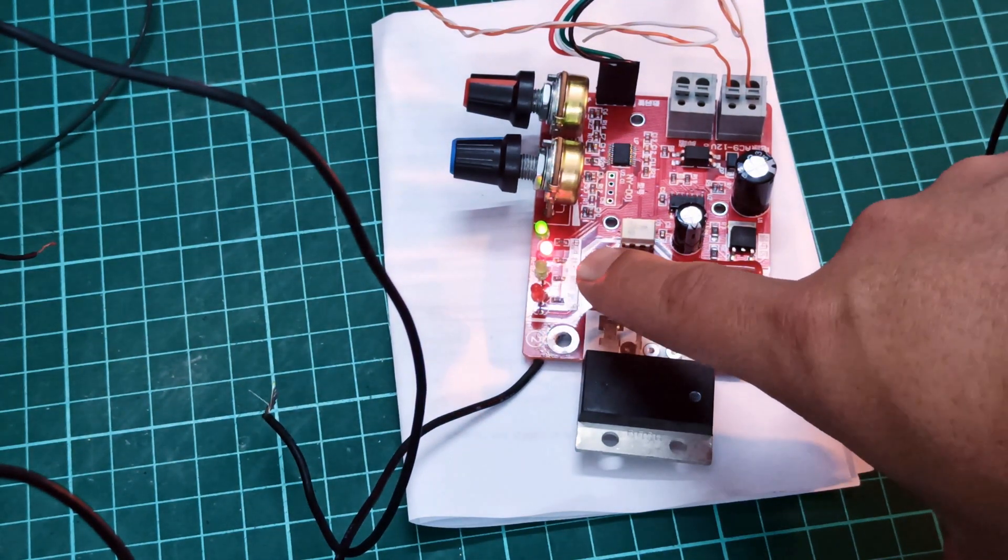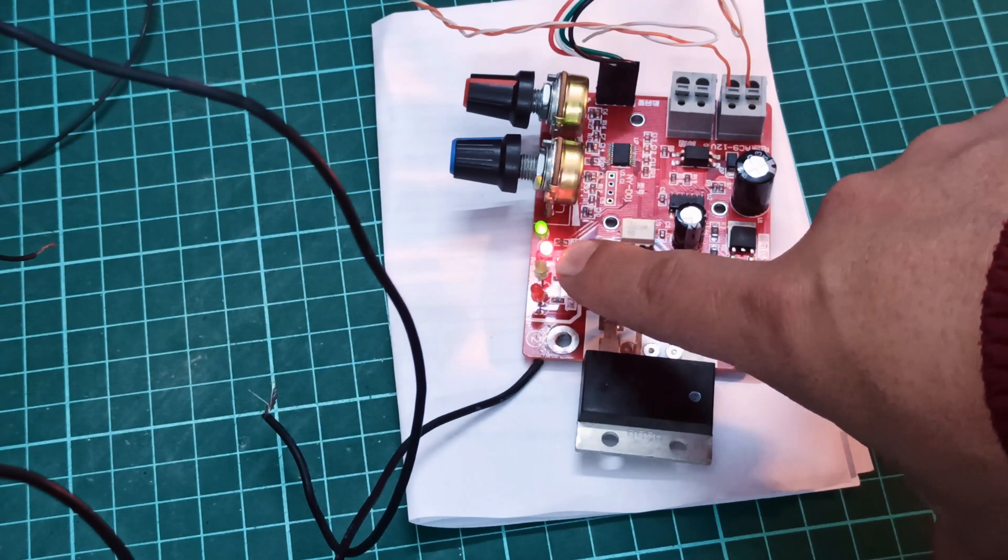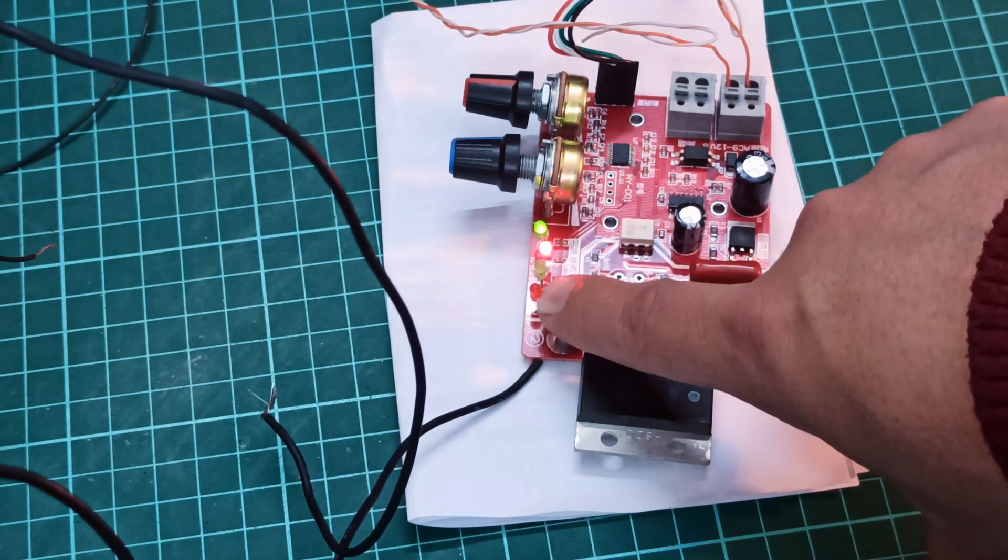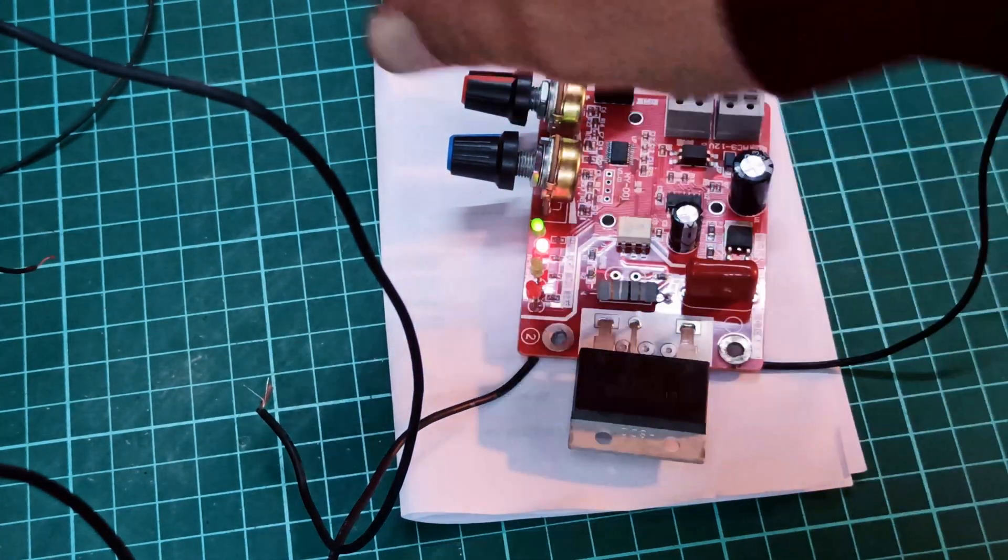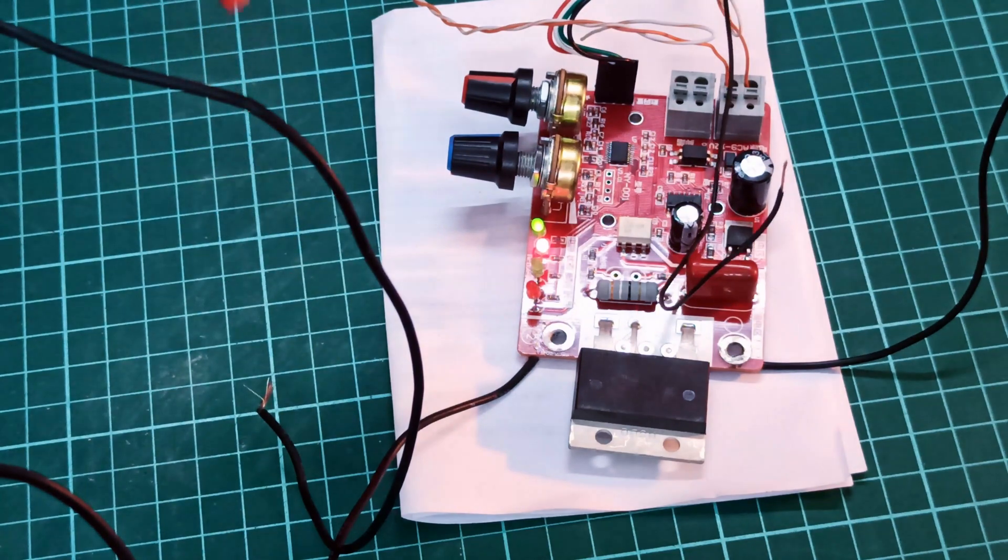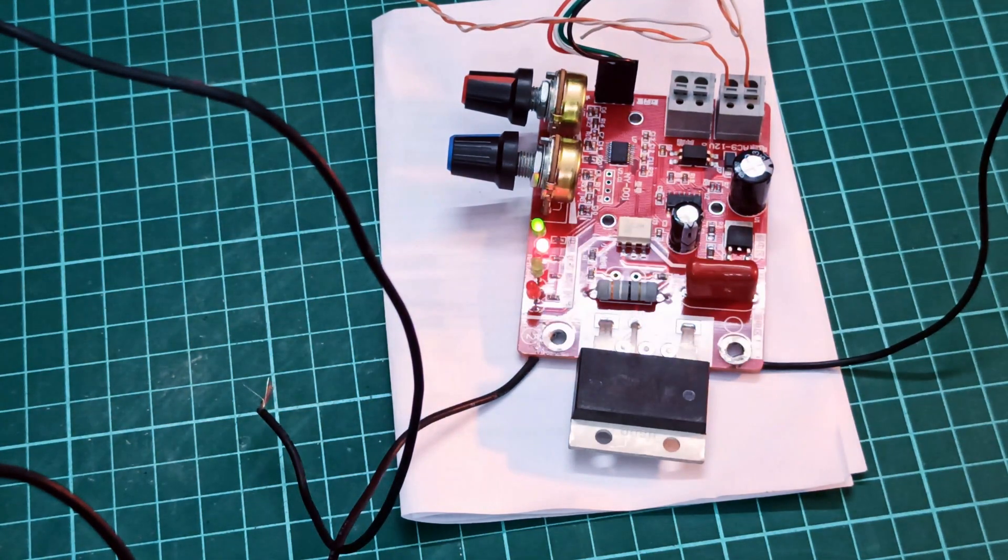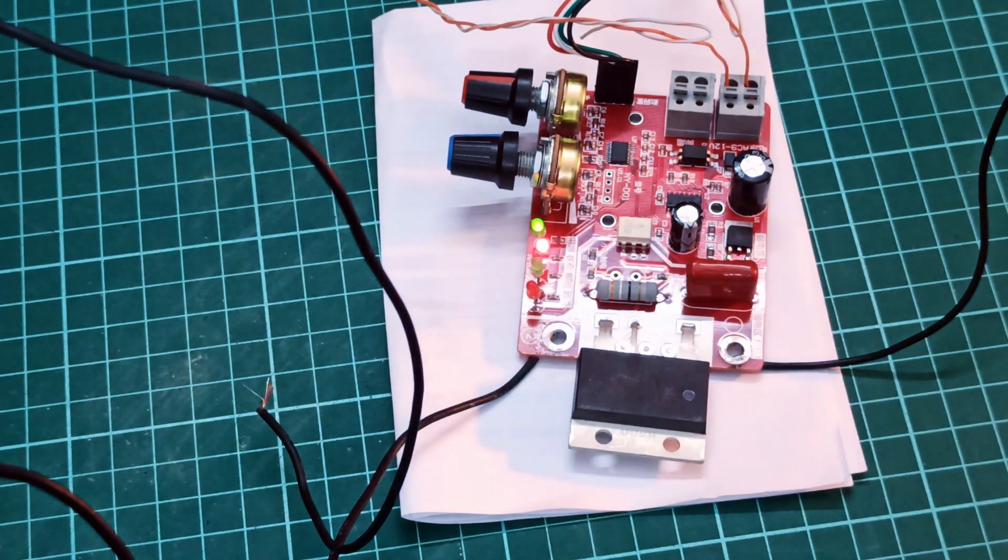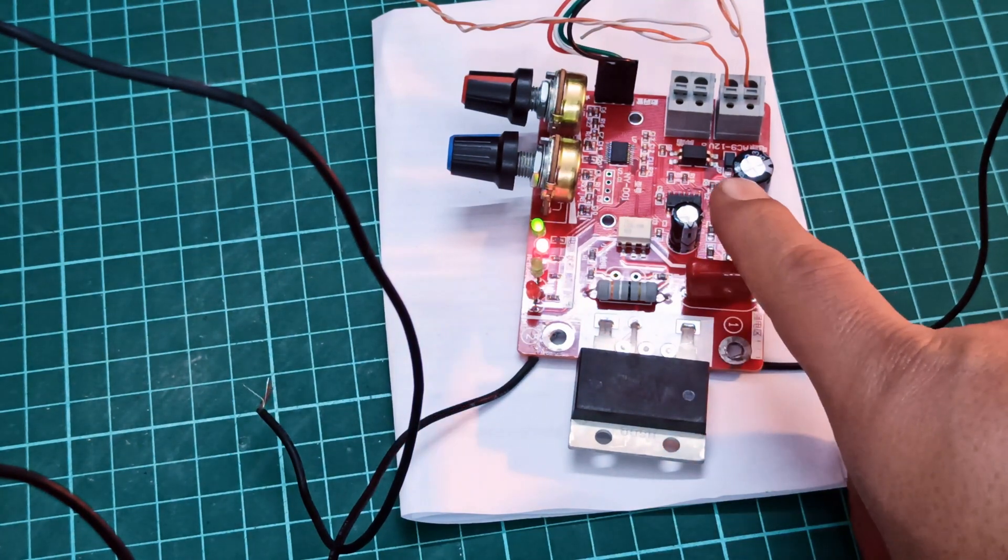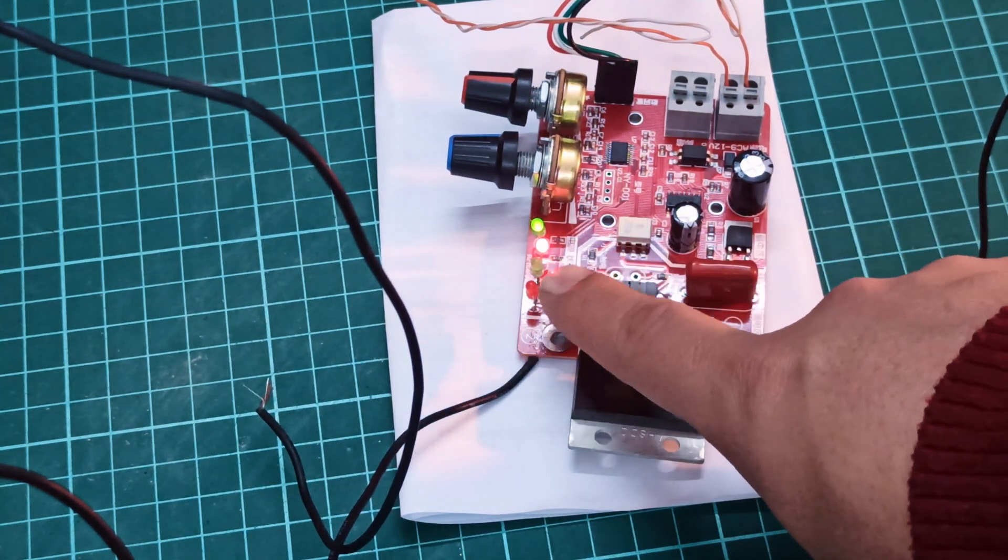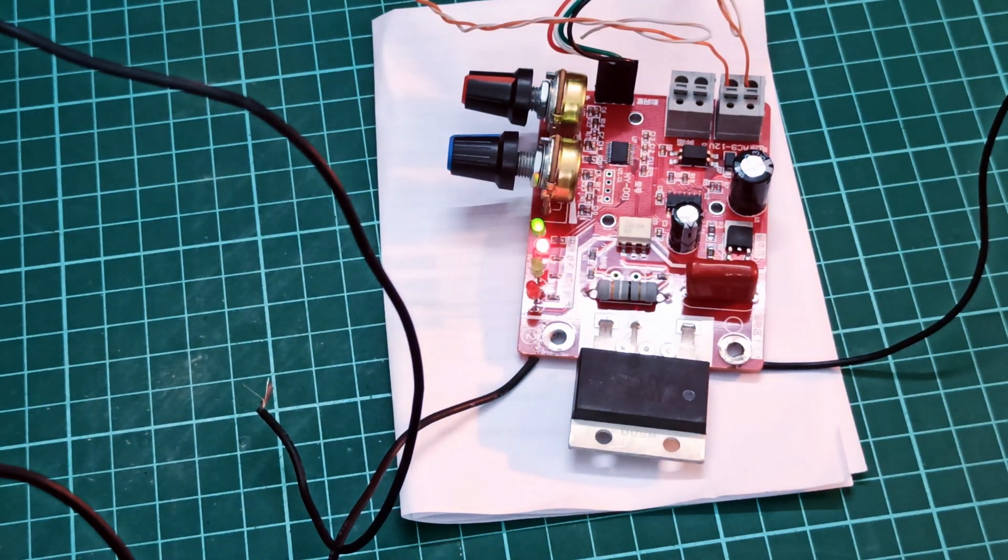Let me zoom in a little bit. You can see these two LEDs - the third LED is for the continuous pulsating indication while the fourth one is the trigger LED. So whenever you're pressing this trigger switch or using the foot pedal switch, the fourth LED is going to turn on for that amount of time, but no pulses. Since we have no pulses, the third one is not working either.